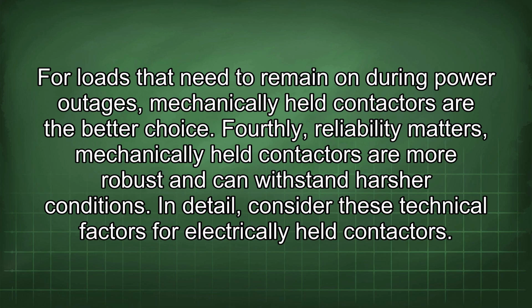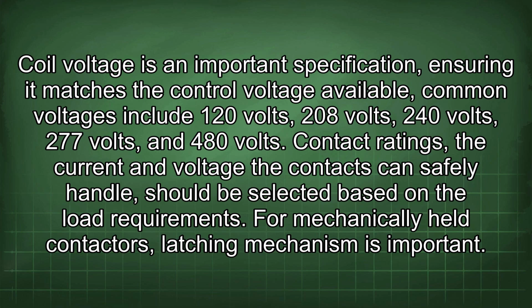In detail, consider these technical factors for electrically held contactors. Coil voltage is an important specification, ensuring it matches the control voltage available. Common voltages include 120 volts, 208 volts, 240 volts, 277 volts, and 480 volts. Contact ratings: the current and voltage the contacts can safely handle should be selected based on the load requirements.